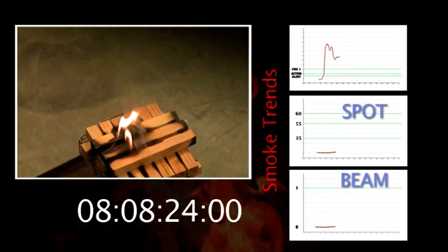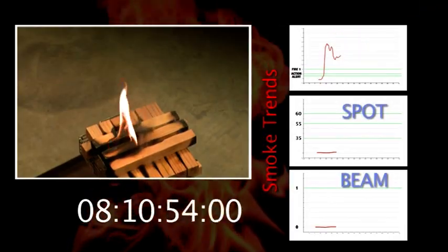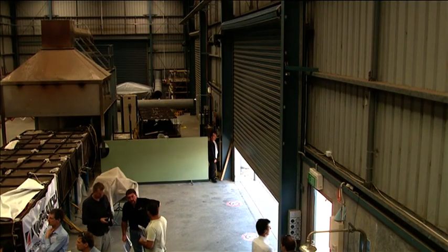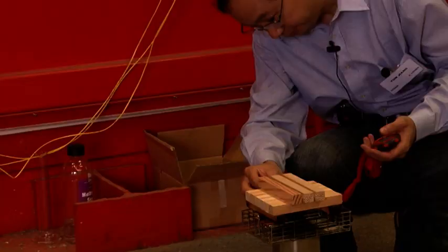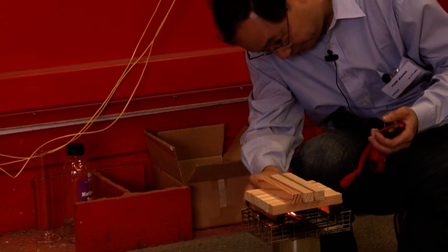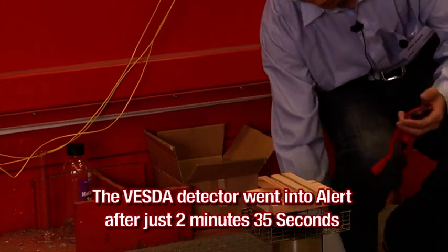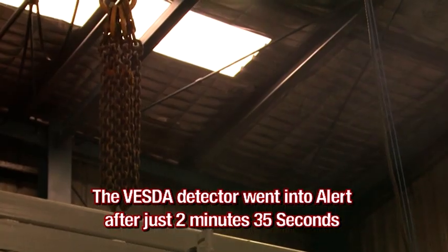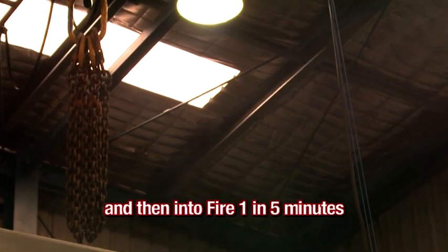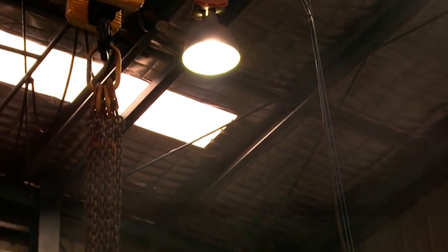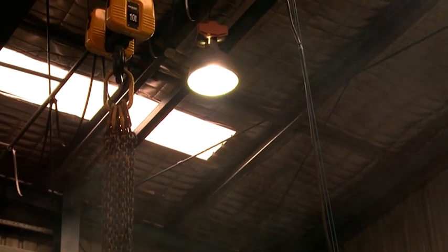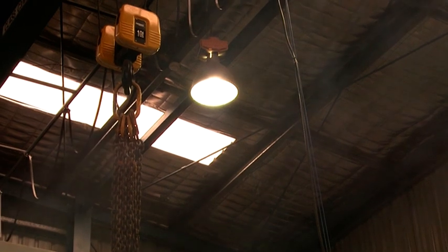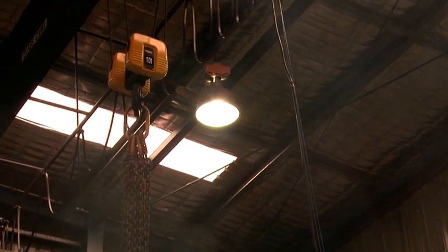Next, the warehouse doors were opened and the same test repeated. This time, the VESDA detector went into alert after just two minutes thirty-five seconds and then to fire one in five minutes. Once again, the VESDA proves superior as the remaining two detectors have still not registered a reading.